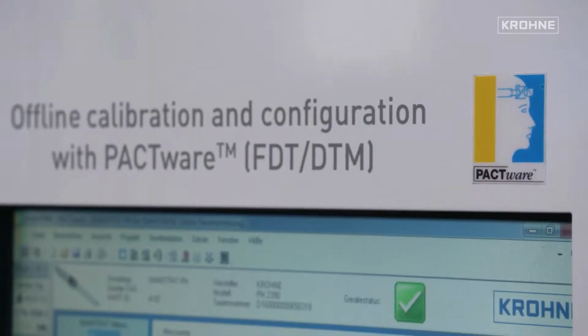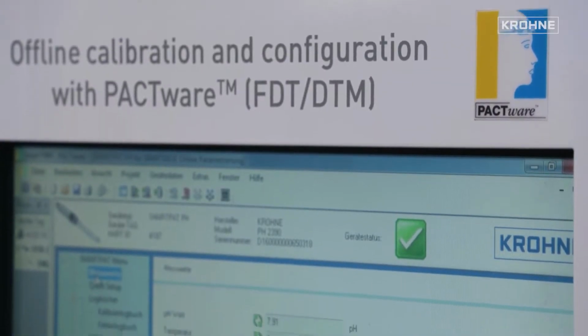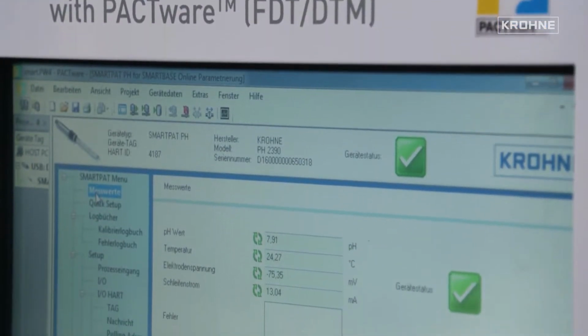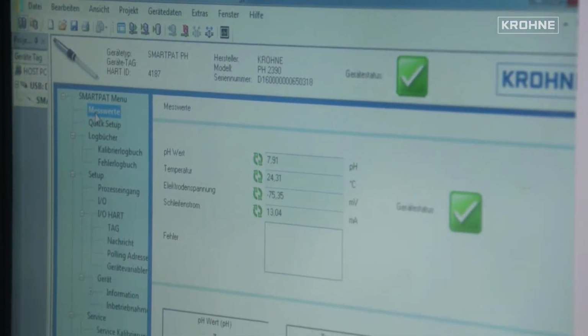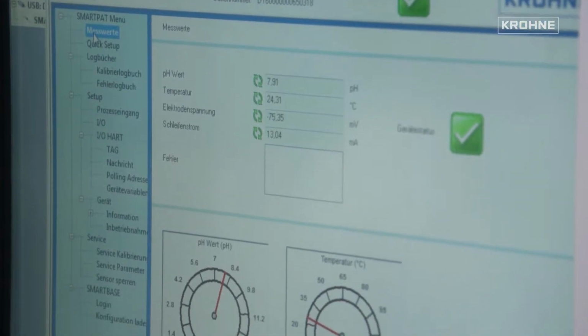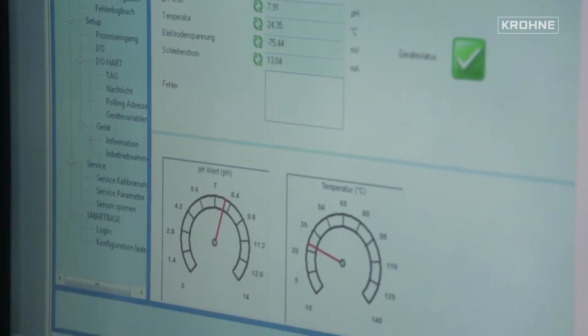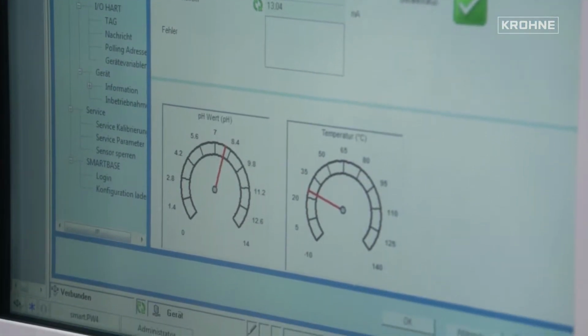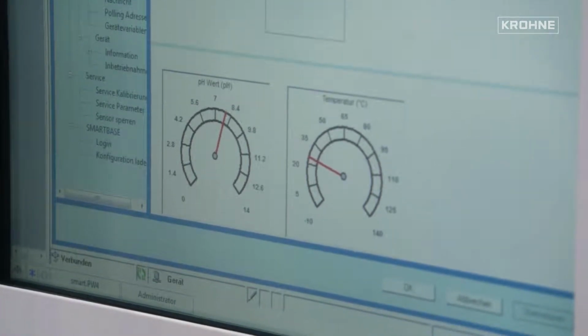But the best way to calibrate a pH probe like that is to do an offline calibration in the lab. That means he has two sensors for each application: one pre-calibrated sensor stays in the lab, while the other is in the application. He just swaps the sensors, so the application is only interrupted for maybe 30 seconds before it's up again, and he takes the used sensor back to the lab.